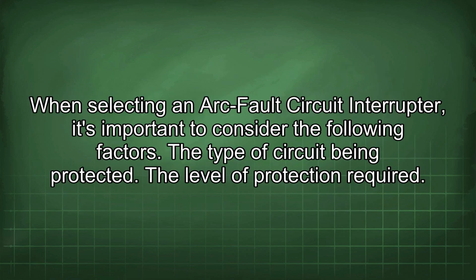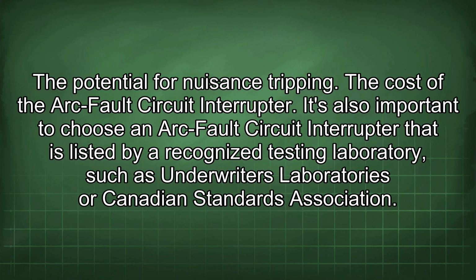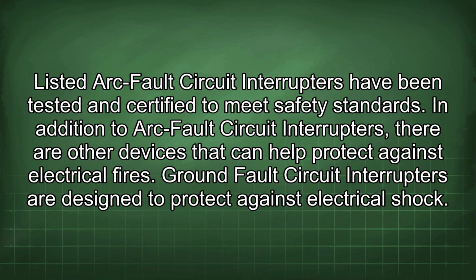When selecting an arc fault circuit interrupter, it's important to consider the following factors: the type of circuit being protected, the level of protection required, the potential for nuisance tripping, and the cost of the arc fault circuit interrupter. It's also important to choose one that is listed by a recognized testing laboratory such as Underwriters Laboratories or Canadian Standards Association. Listed arc fault circuit interrupters have been tested and certified to meet safety standards.